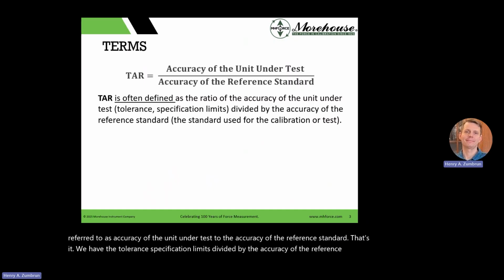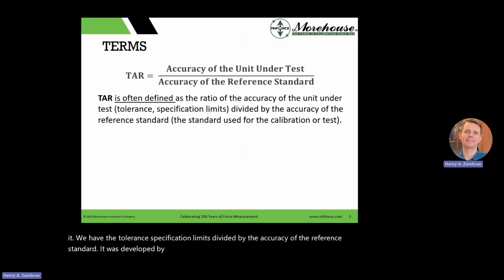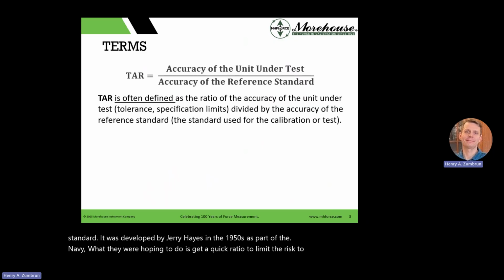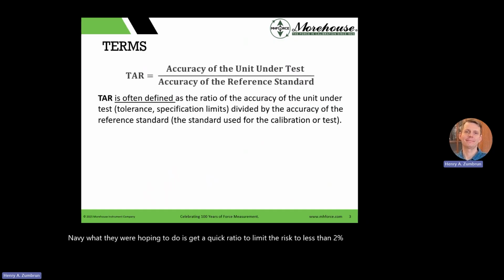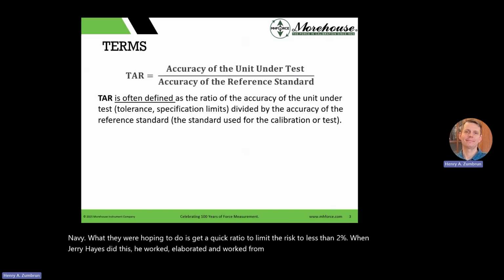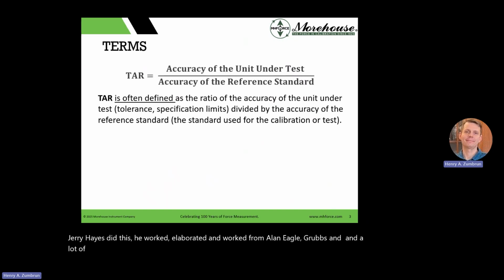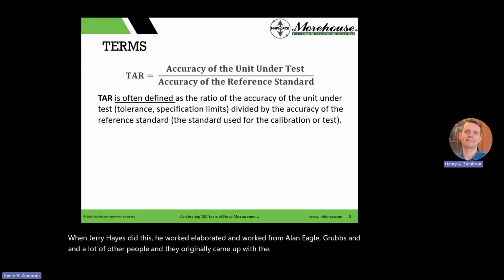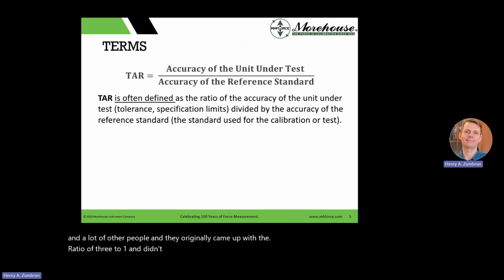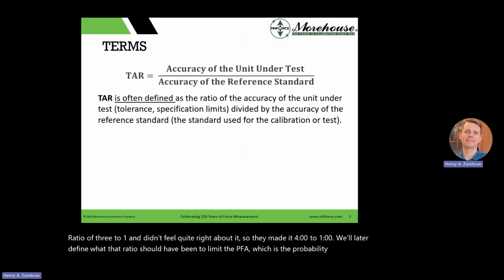It was developed by Jerry Hayes in the 1950s as part of the U.S. Navy. What they were hoping to do is get a quick ratio to limit their risk to less than 2%. When Jerry Hayes did this, he elaborated on work from Alan Eagle, Grubbs, Kuhn, and a lot of other people. They originally came up with a ratio of 3-to-1 and didn't feel quite right about it, so they made it 4-to-1. We'll later define what that ratio should have been to limit the PFA, which is the probability of false accept, to less than 2%. Well, let's move on.